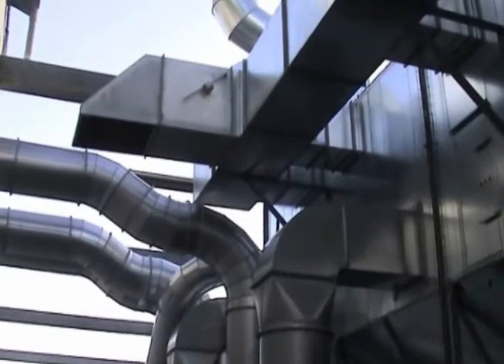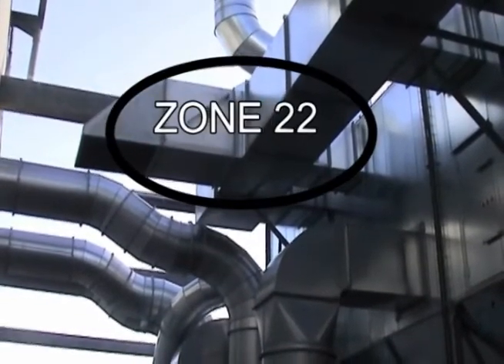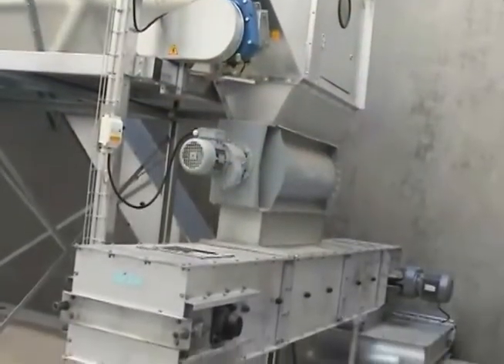The filter raw gas section will often contain explosive dust concentrations, so zone 20 applies here. The clean air section, on the contrary, will be without dust and is ruled by zone 22. Normally the filter does not contain ignition sources, but it is protected with explosion relief doors should an explosion start due to hot or unplanned particles.